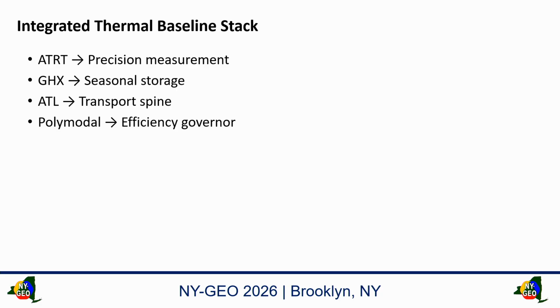It can be something like an air-to-water heat pump unit that gives me hot water from the outside air, or cold water from the outside air. I can temper the loop with that. And for that last 10% of the year, I don't have to run it very much. But it does have capital expenditure. And if it's cheaper than an additional ground heat exchanger, it makes sense. It can be a polymodal heat pump, one that does air source cooling, water source cooling, and moves the heat bidirectionally between the outside air and the water loop. I have a patent on that process.